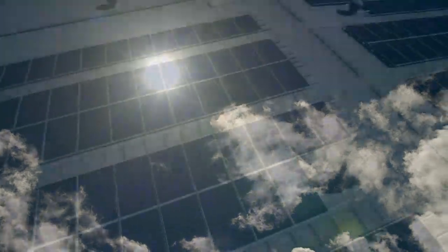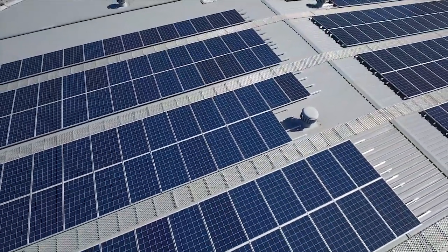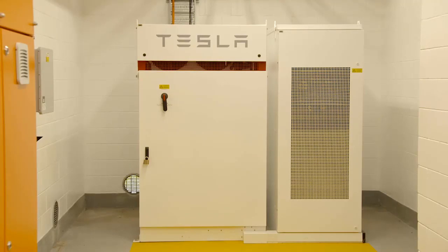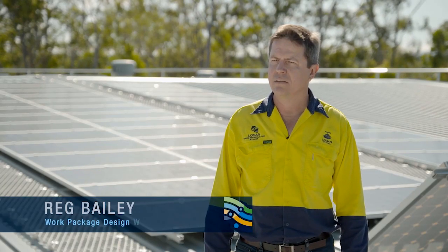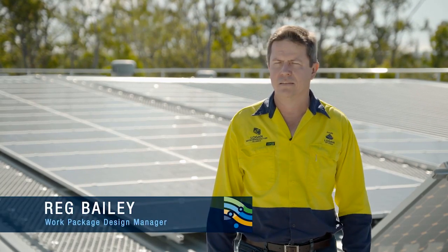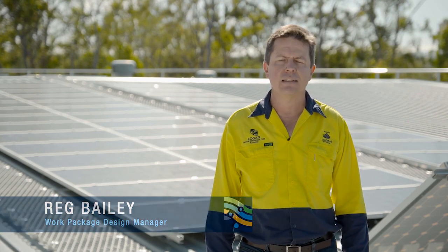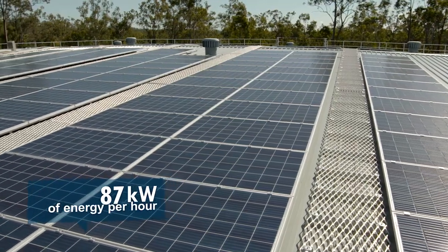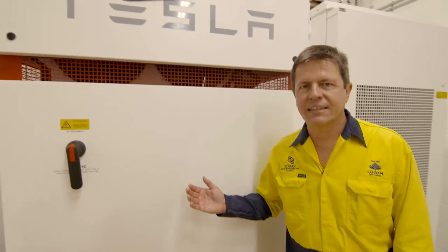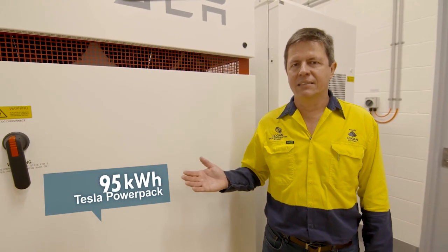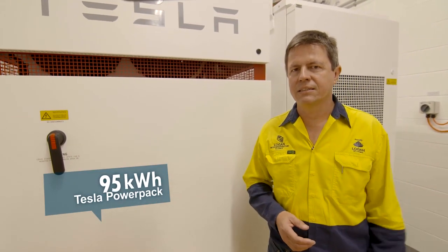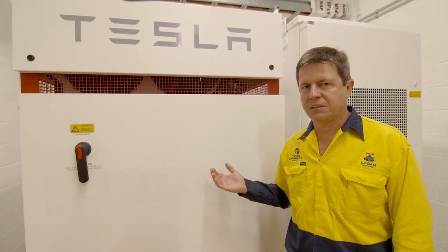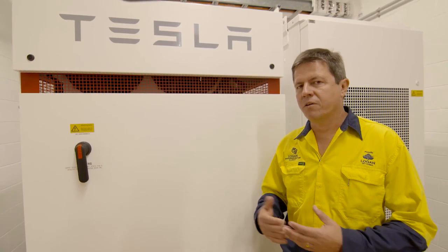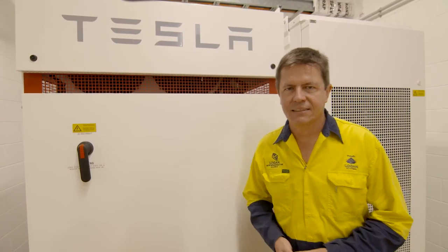Power comes from the sun, captured in an on-site solar array and stored in a commercial battery. There are 323 panels on the roof that has sufficient capacity to produce 87 kilowatts of energy every hour. This is our 95 kilowatt hour Tesla power pack. It manages the output from our 3 inverters, and it has a battery capacity to meet the demand from the site for up to 3 days.